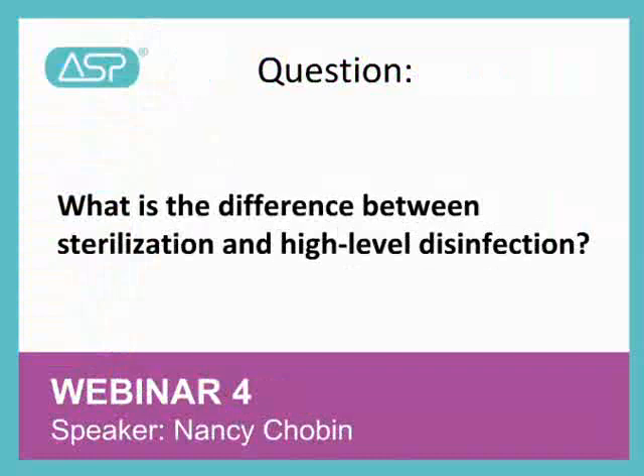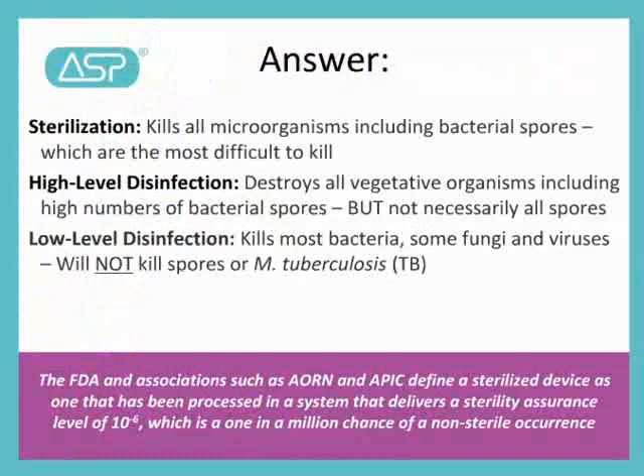And another question we received is, what is the difference between sterilization and high-level disinfection? With sterilization, all microorganisms are killed, including bacterial spores, which are the most difficult to kill. With high-level disinfection, all vegetative organisms are destroyed, including high numbers of bacterial spores, but not necessarily all spores. And with low-level disinfection, most bacteria, some fungi and viruses are killed, but not spores or Mycobacterium tuberculosis.